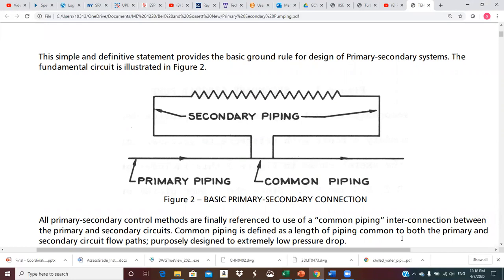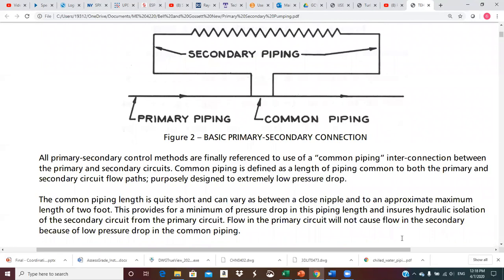We have to establish the very basic principles here, and that's what this first figure two diagram is all about. This discussion provides a basic ground rule for primary-secondary systems. The fundamental circuit is shown in figure two. All primary-secondary control methods are finally referenced to the use of a common pipe interconnection between primary and secondary circuits.